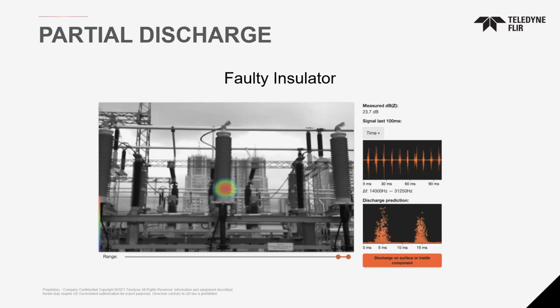Because those are going to send off different discharges, different vibrations off that device if it is dirty. But if it is clean, then you might really have an issue here, and you would want to schedule that downtime. Here we see that the camera has done this analysis, and it is actually a discharge on or inside the component, which are the ones that we want to focus on and make sure that these get repaired.